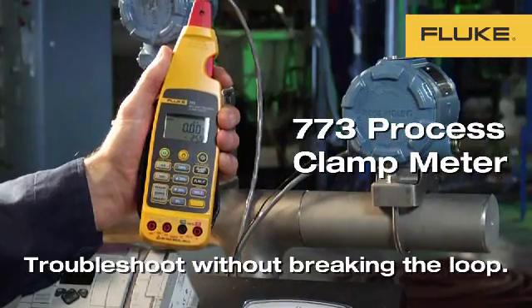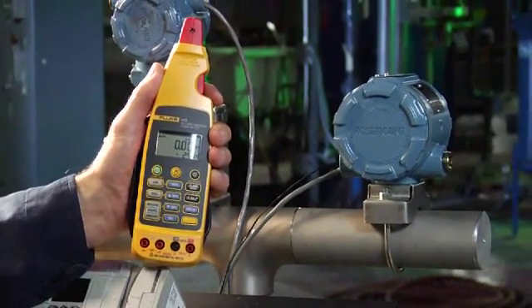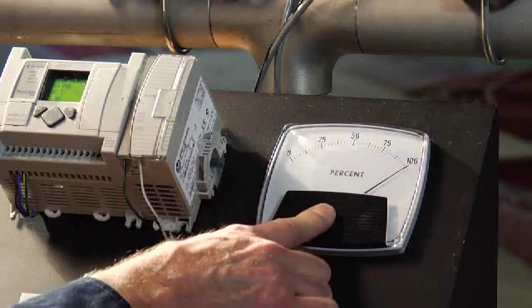The Fluke 773 process milliamp clamp meter is great for troubleshooting without breaking the loop. The local indicator shows that the process loop in a temperature transmitter is in alarm.